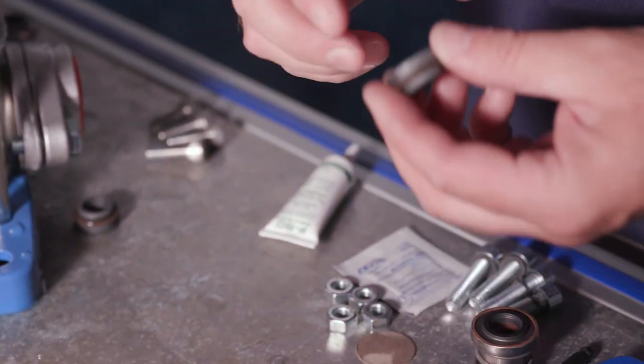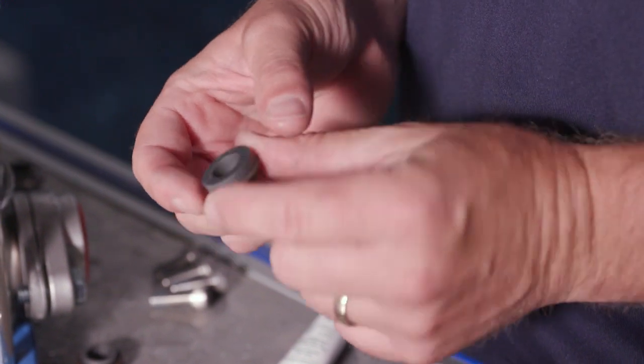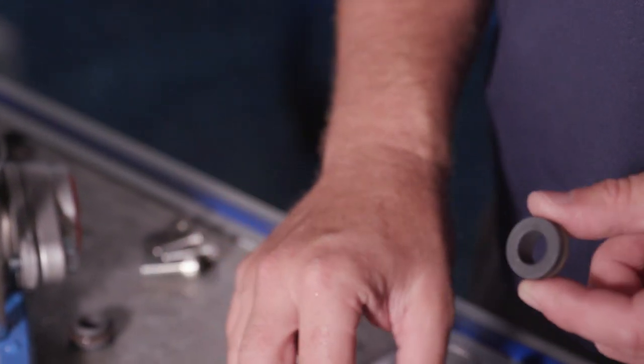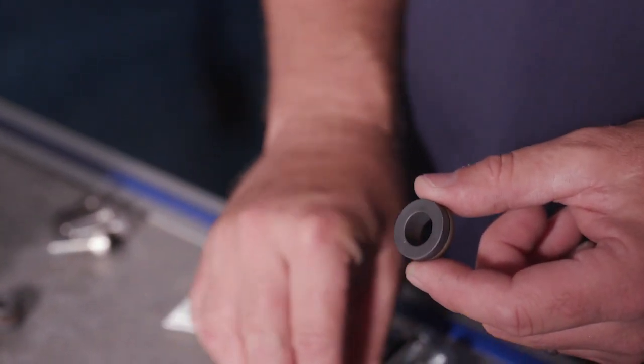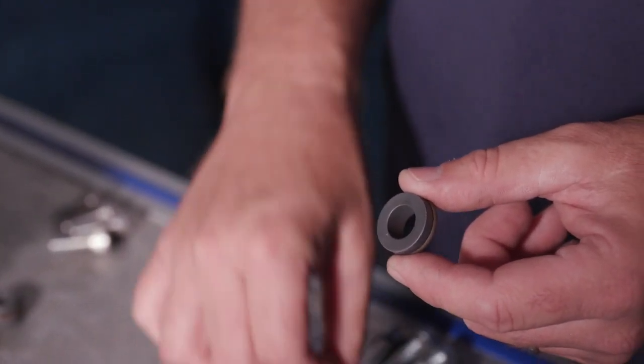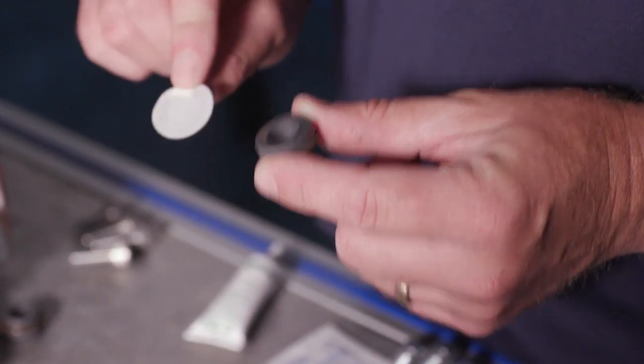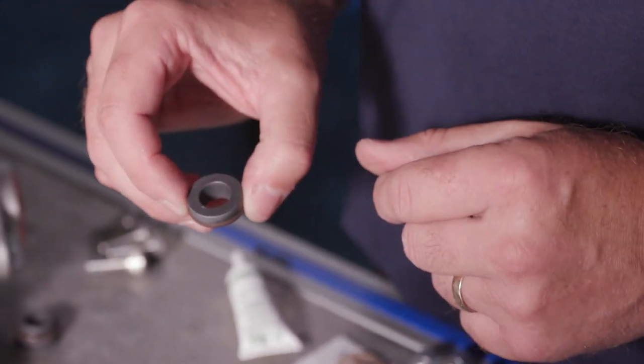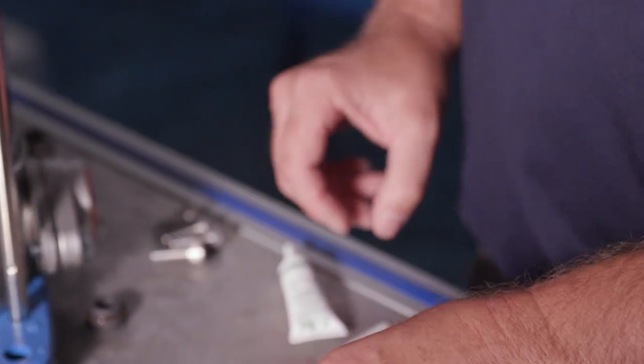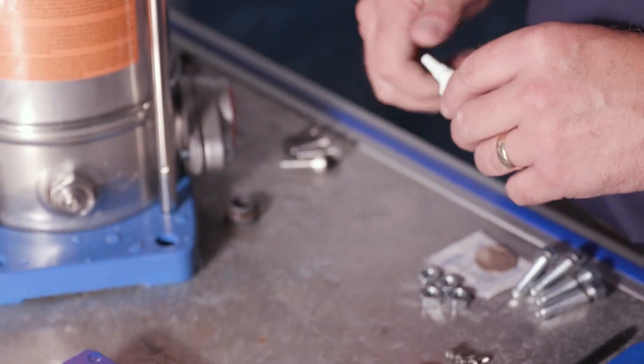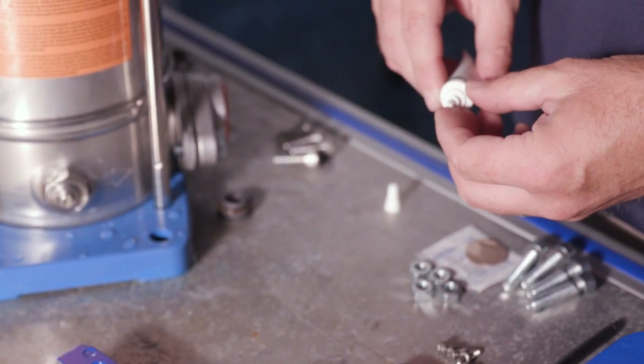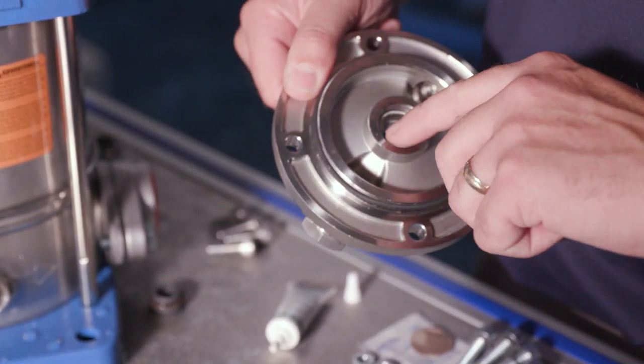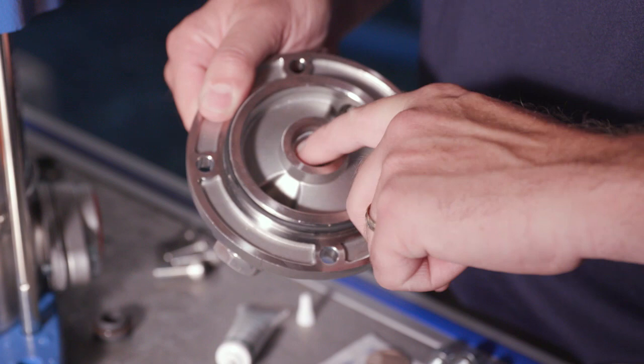Here's our stationary portion here. You do want to minimize touching the seal faces, and one sort of nice thing about this little piece of cardboard that comes with the seal, you can use that to press it in. We're going to wipe off the faces at the end anyway. We're going to use a little bit of P80 to lubricate just a little bit of the bore.